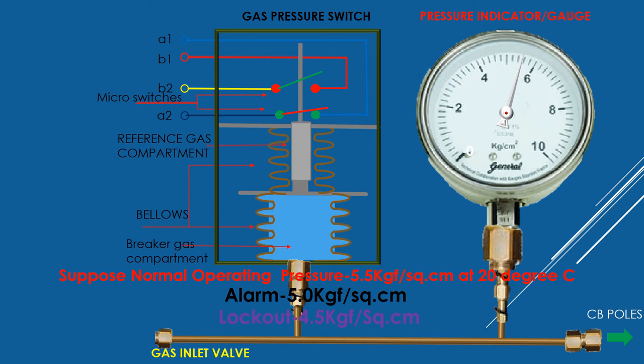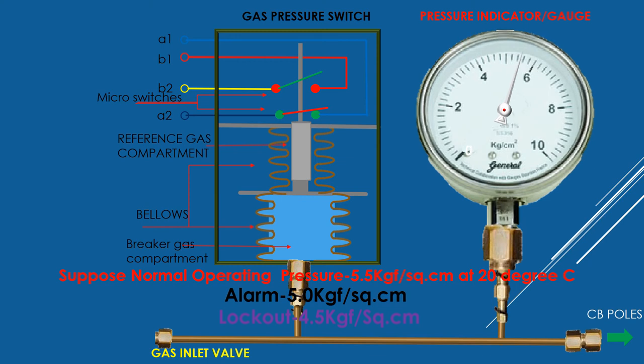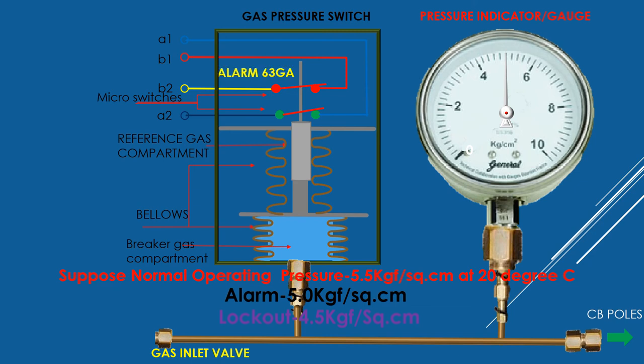One switch is used as the alarm circuit, designated 63GA, between connecting points B1 and B2. Gas pressure is gradually decreasing and the alarm appears first, then lockout. The second switch is used as the lockout, designated 63GL, with connecting points A1 and A2.